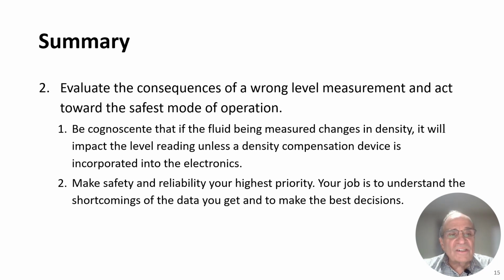In continuing the summary, evaluate the consequences of a wrong level measurement and act towards the safest mode of operation. Be cognizant that if the fluid being measured changes in density, it will impact your level reading unless a density compensating device is incorporated into the electronics. Make safety and reliability your highest priority. Your job is to understand the shortcomings of the data you get and to make the best decisions.